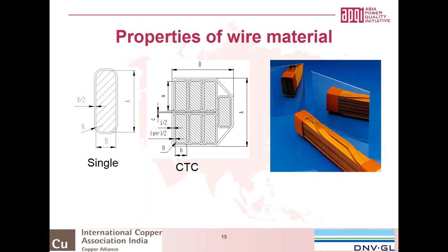If you look at the material, how are the windings often made? They are often made of copper, and for small transformers they will usually use a single wire, but in case you have larger transformers with high currents, you will often use a CTC cable, which is a combined cable, where you have a small area of copper in each strand, but in total it's a large area. They are all in parallel. And the picture on the right side shows you how such a cable is made. And sometimes you will see that they are also wrapped with paper, and sometimes with epoxy around it for insulation.